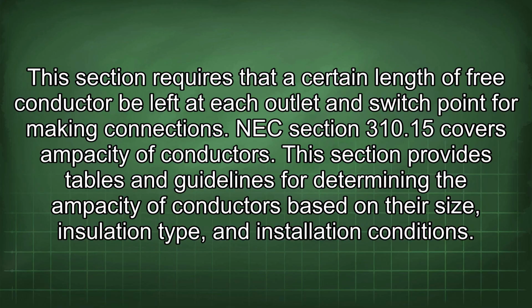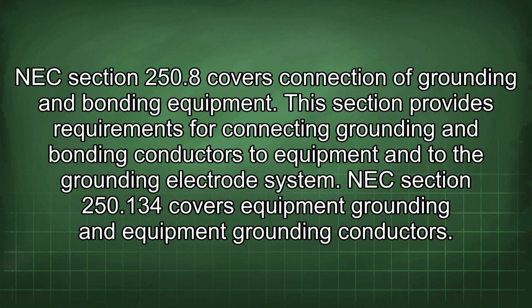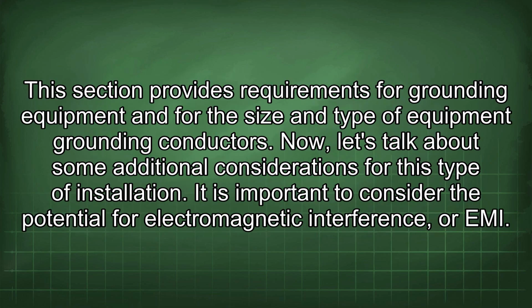This section provides tables and guidelines for determining the ampacity of conductors based on their size, insulation type, and installation conditions. NEC Section 250.8 covers connection of grounding and bonding equipment. This section provides requirements for connecting grounding and bonding conductors to equipment and to the grounding electrode system. NEC Section 250.134 covers equipment grounding and equipment grounding conductors. This section provides requirements for grounding equipment and for the size and type of equipment grounding conductors.